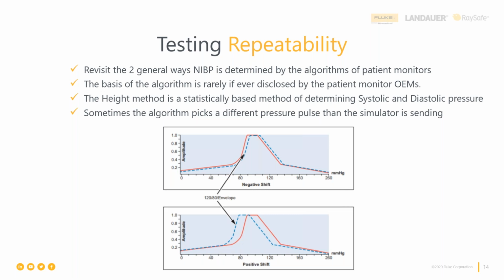All right. You need to be thoughtful about just things like I explained about, say, cuffs with bladders versus cuffs that don't have bladders. Leaky cuffs that have been stuck with a needle and you can't really see the leak. It's a very slow little leak, and you don't have time to take that cuff and submerge it underwater to see the leak.